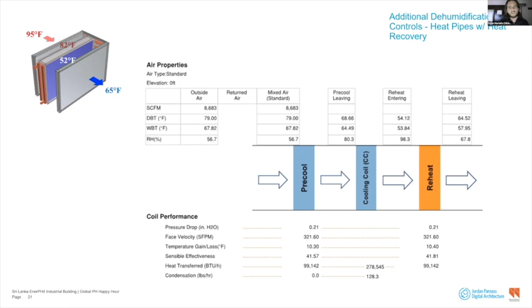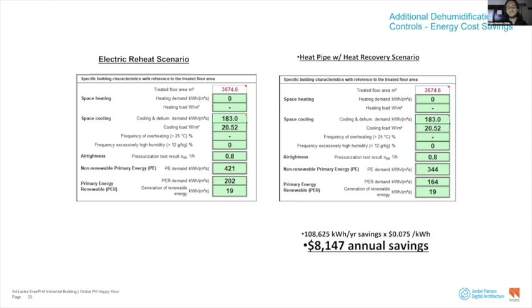So here is an analysis that we had done looking at an electric reheat scenario on the left versus the heat pipe scenario on the right. And you can see the primary energy demand dropped from 421 kilowatt hours per meter square per year down to 344. So a significant reduction in both source energy use and also, as we show below, annual energy consumption of about 108,000 kilowatt hours per year, which translates to roughly $8,000, which is certainly not nothing, especially in a region like this. That's certainly a huge chunk of savings. Next slide. I'm going to hand it back off to Jordan.